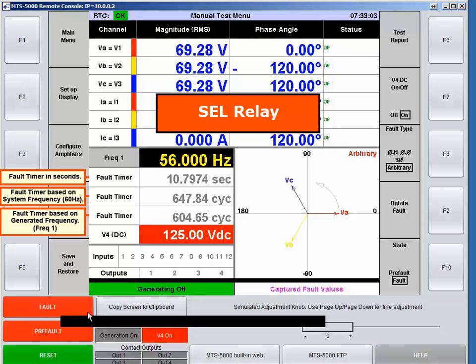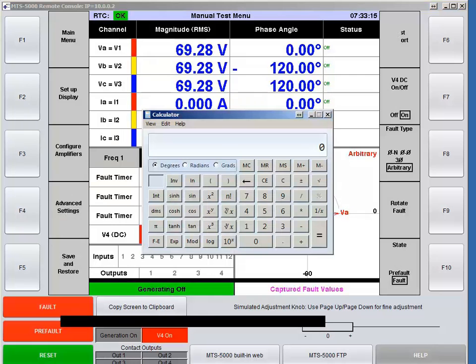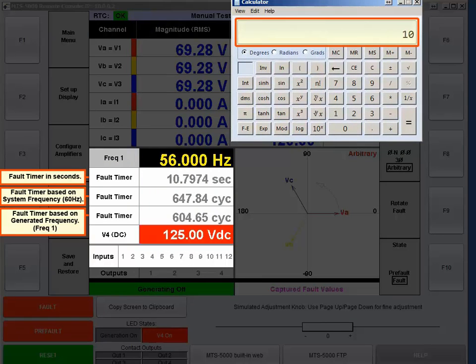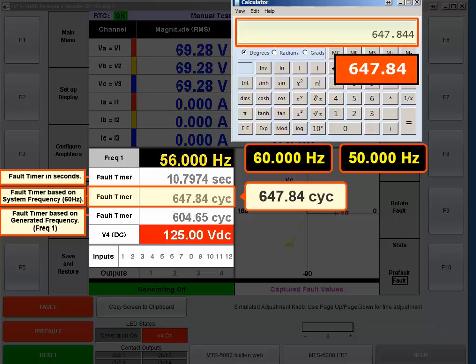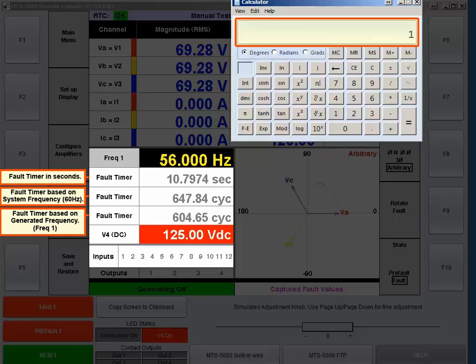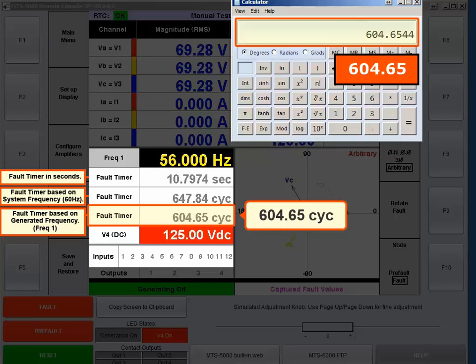If you ever want to know how your timer works on your test set, get both values on screen at the same time, then use a calculator. For example, 10.7974 times 60 Hz equals 647.84 cycles — if your timer matches that, your test set is working on 60 Hz or system frequency. Alternatively, 10.7974 times 56 Hz gives 604.65 cycles. That's how the two timers work together.